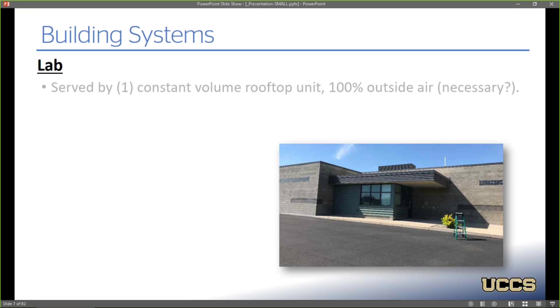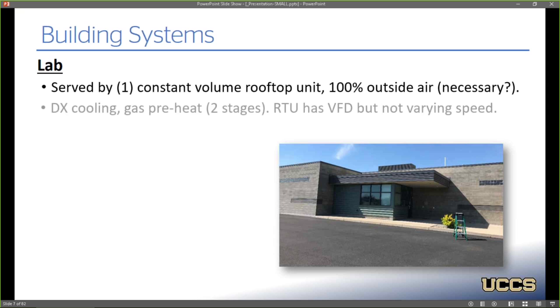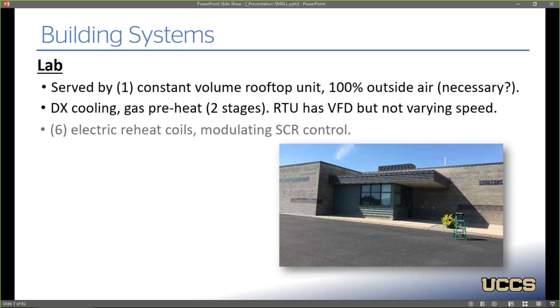And then moving over to the lab, this is served by a single constant volume rooftop unit that's 100% outside air. Whether or not that's necessary is really a question because they don't really use this very extensively as a lab building, so that 100% outside air is likely excessive. That RTU also has DX cooling and gas preheat, again 2 stages each. It does have a variable frequency drive on the supply fan, but it's not actually used to vary the speed at all, so it is a constant volume system. And that's serving 6 electric reheat coils that have modulating SCR control, so they do have very good control over the supply air temperature.